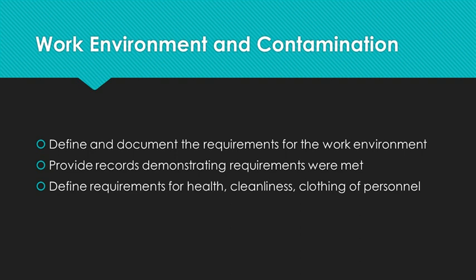If you have a manufacturing area that needs to be kept at positive pressure, you will need records demonstrating that pressure was held 24/7, 365. In addition, the company needs to define requirements for health, cleanliness, and clothing of personnel in product contact areas where the device safety or performance could be affected.